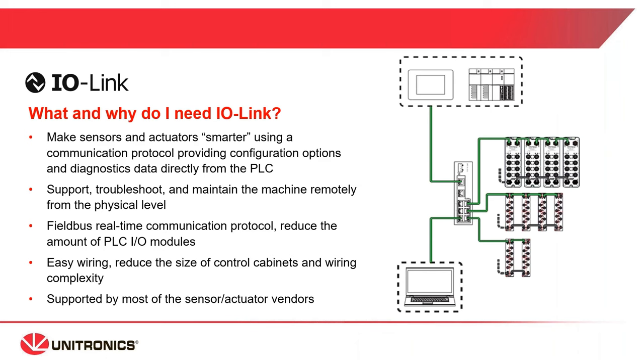IO-Link is an IEC standard communication protocol used for sensors and actuators. It is widely used in the industry by most sensor and actuator manufacturers. Using this technology, we can make sensors smarter and more informative than just binary or simple analog information sensors. For example, a simple IO-Link photo sensor can give us the element distance, the ambient temperature, and even the glass transparency of the sensor for maintenance reasons. We can also change the sensor operation mode directly via the PLC using the IO-Link communication.